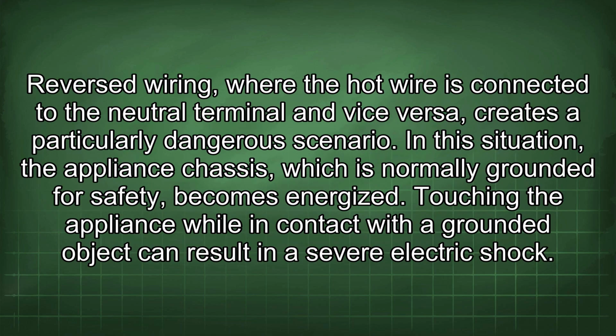Reversed wiring, where the hot wire is connected to the neutral terminal and vice versa, creates a particularly dangerous scenario. In this situation, the appliance chassis, which is normally grounded for safety, becomes energized. Touching the appliance while in contact with a grounded object can result in a severe electric shock.